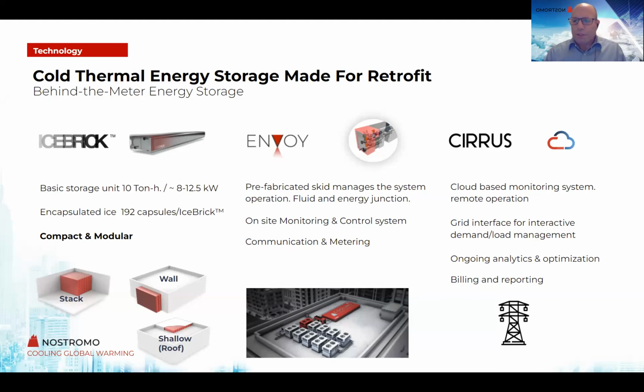It has three components. The first is the patented ice brick, which stores the energy in the form of encapsulated ice. Each unit is about 14 feet long and stores about 10 ton-hours of cold energy, equivalent to about 10 kilowatt hours on average. The system will typically consist of more than 100 bricks, so this means megawatt-hour scale systems.